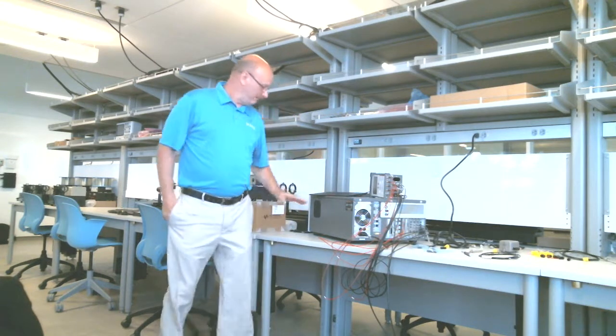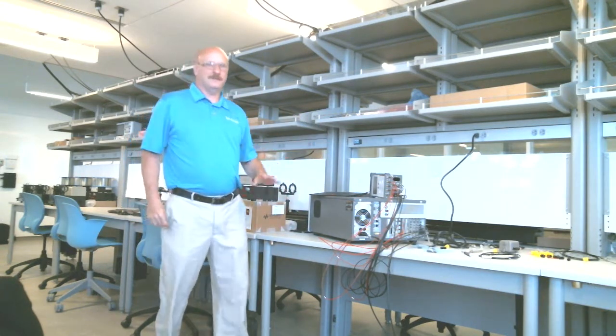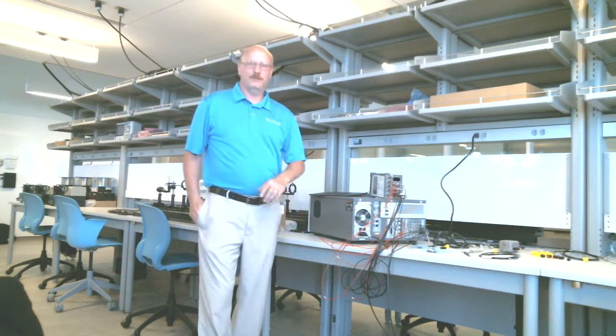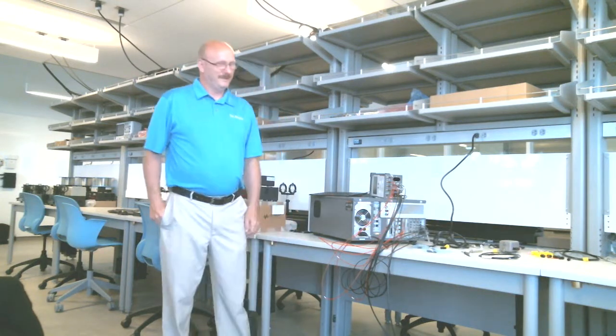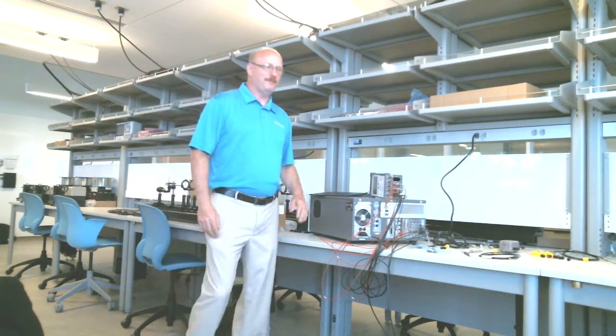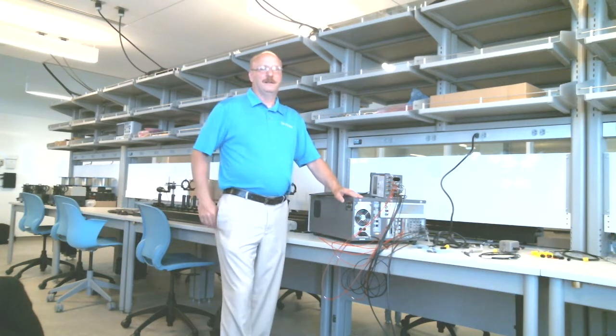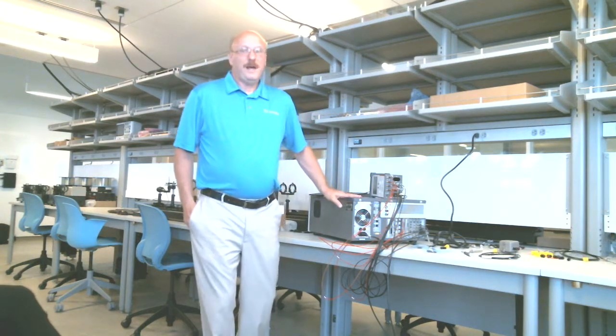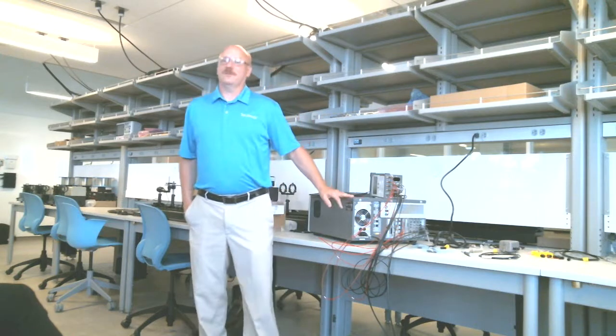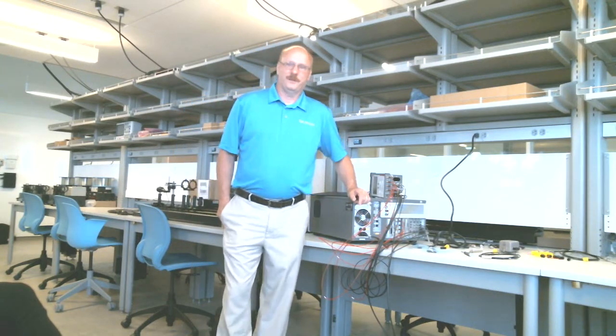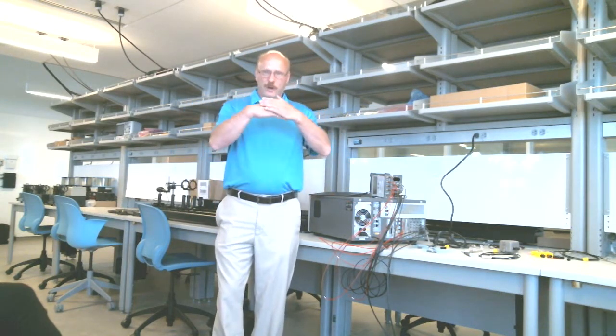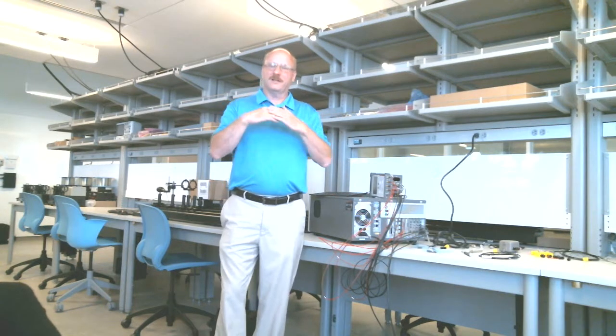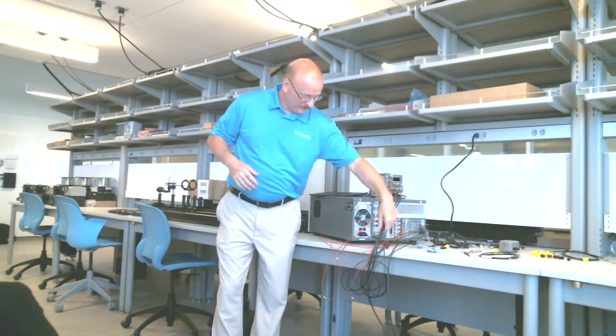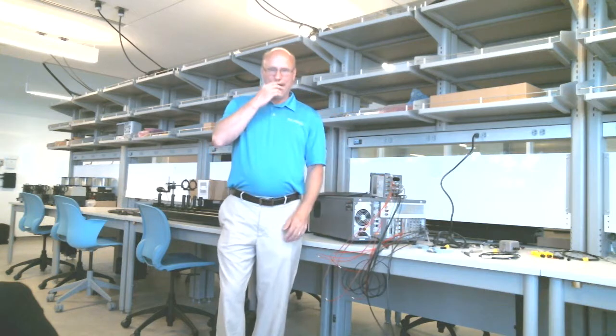You don't want to have vacuum pumps near your cables, or anything like that - I've seen that too, with an air compressor nearby. Keep that stuff away, because it will pick that up. Not electrical noise, but mechanical - you're getting triboelectric effects from the cable, the rubbing of the insulator against the conductor. That's what happens whenever these cables move.